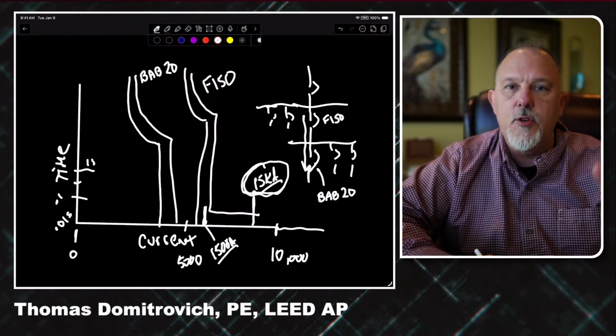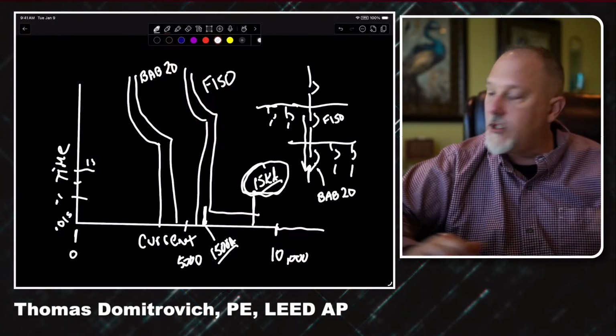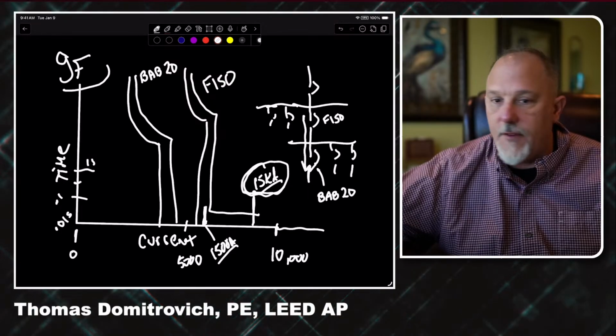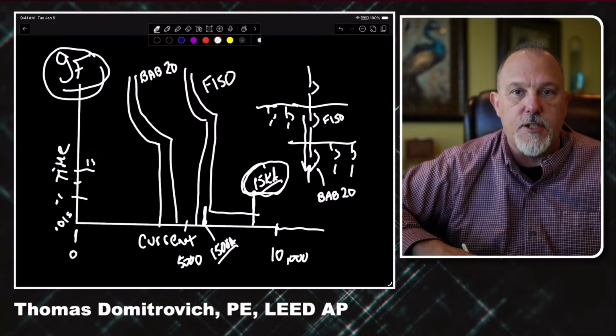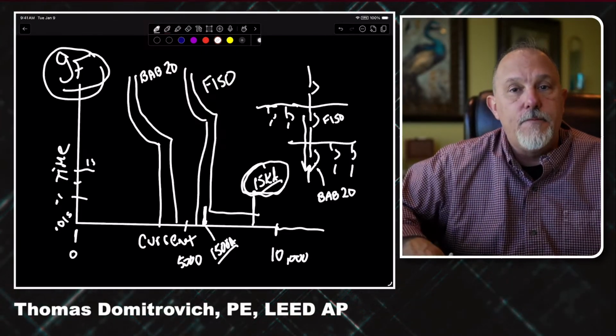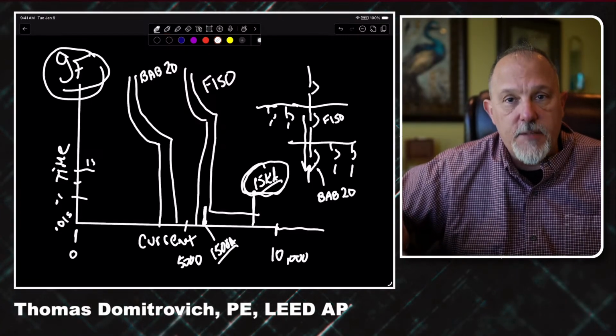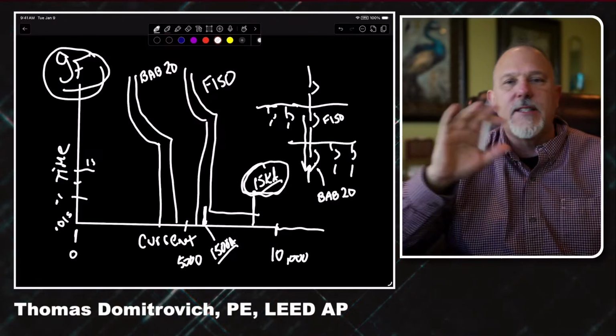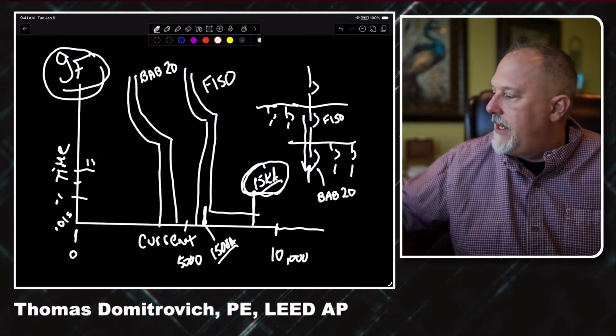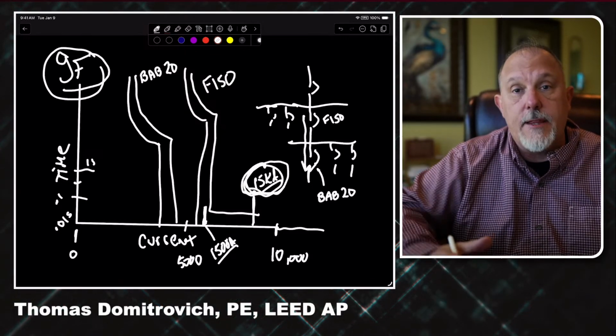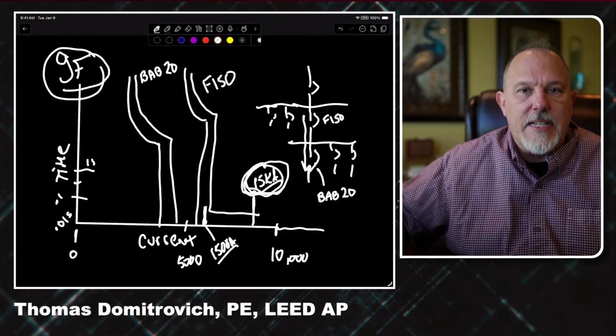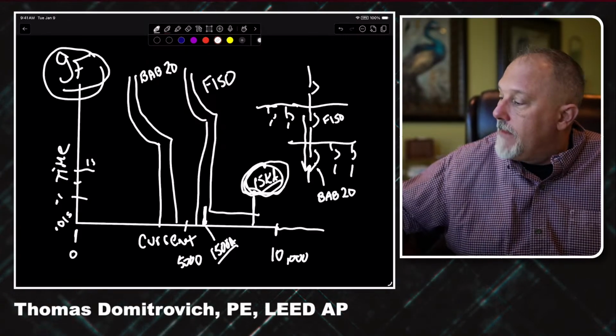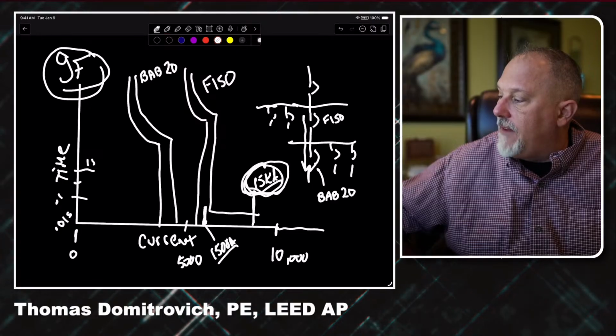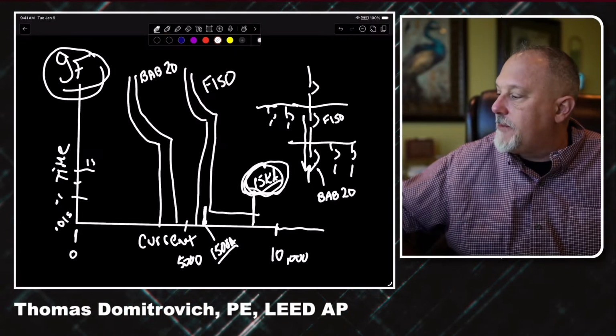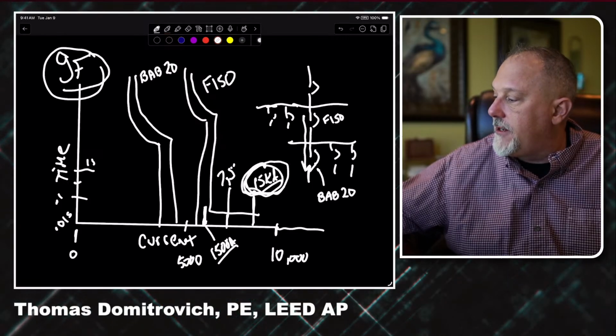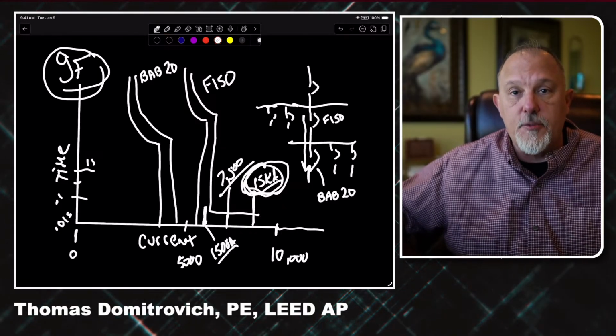So my question was, what's the most common fault in any power distribution system? And his answer was the ground fault. The ground fault is the most common fault in any power distribution system, hands down. So I said, all right, what percentage of the three-phase bolted fault is a typical ground fault? And he was like, well, 70, 60 some percent. Instead of 15,000 amps, which he had said is the most common fault current you would see on these types of panels in a commercial healthcare world, his argument was that the ground fault current's around 60 some percent. I said, let's make it easy. Let's make it 50%. That would be this 7,500 is your most common fault in a power distribution system.